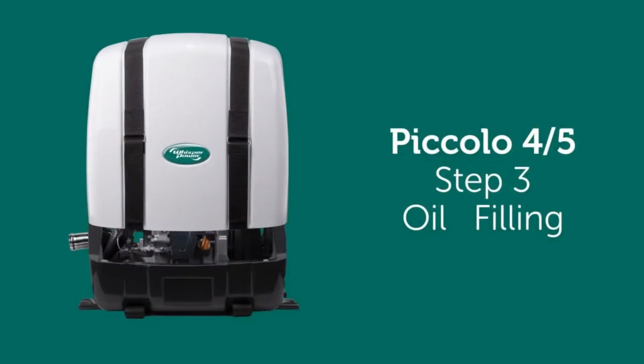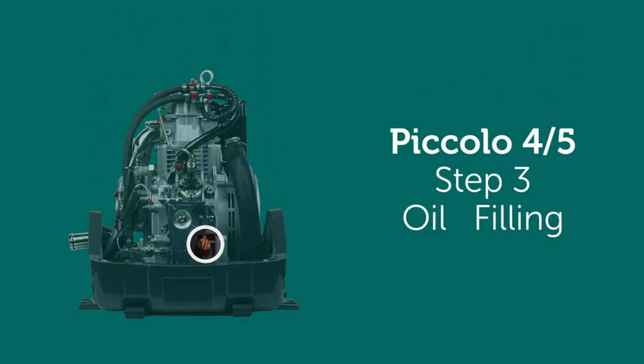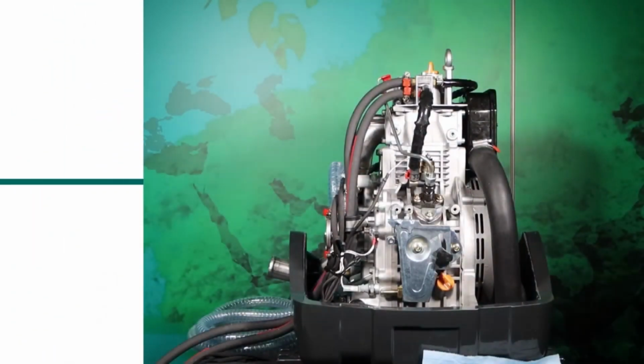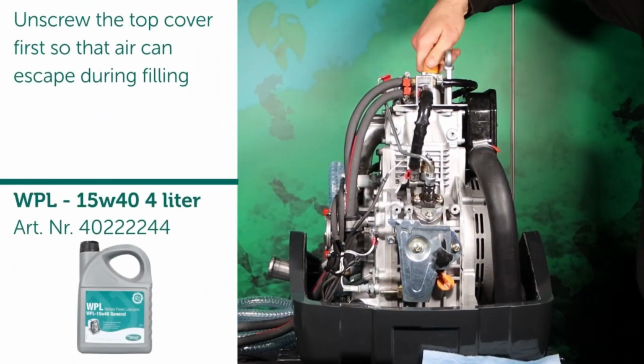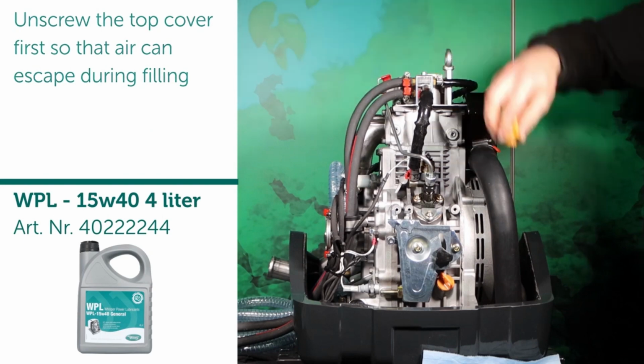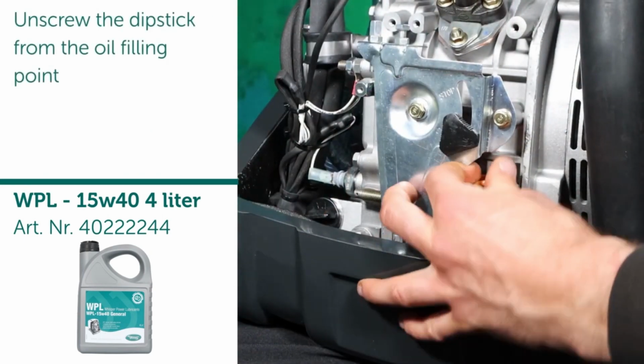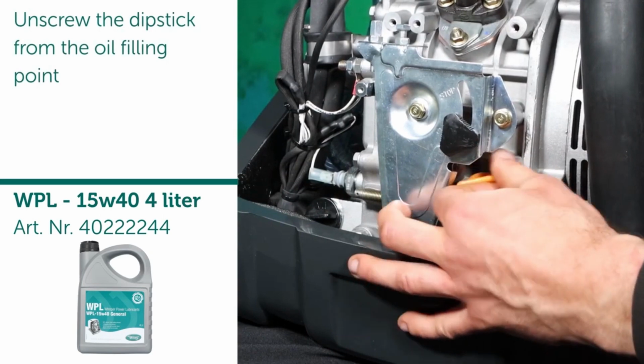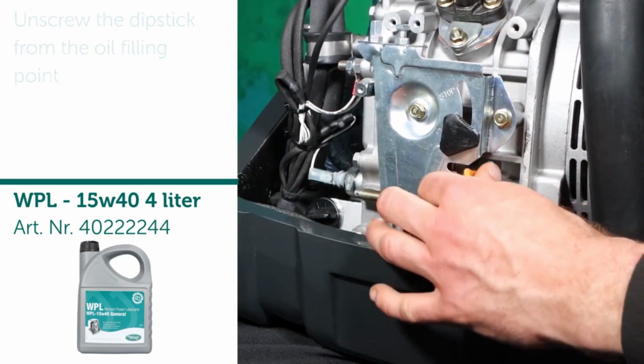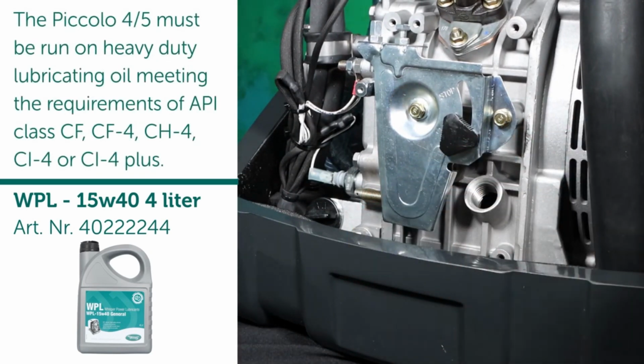Step 3. Oil filling. Unscrew the top cover first, so that air can escape during filling. Unscrew the cover from the oil filling point. The Piccolo 4/5 must be run on heavy-duty lubricating oil, meeting the requirements of API Class CF, CF4, CH4, CI4 or CI4+.